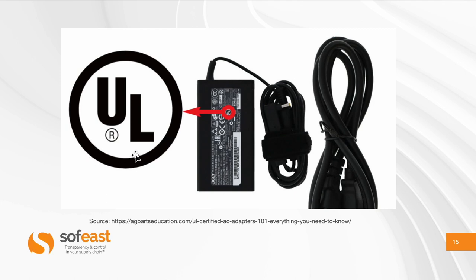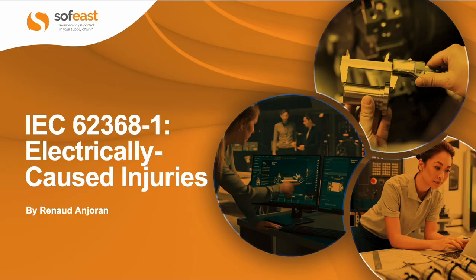For the North American market, UL, CSA, ETL, MET, SGS, TÜV and others are NRTLs allowed to certify. For the EU, CE under the Low Voltage Directive may be sufficient. Basically, take a serious supplier for the power source, make sure it's pre-certified, double-check the certificate — and that's it for this training course. I hope it was useful. Thanks.